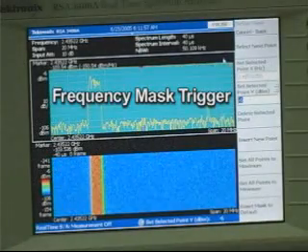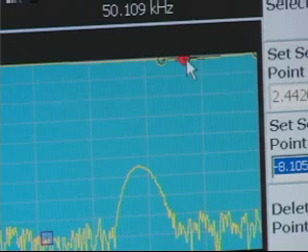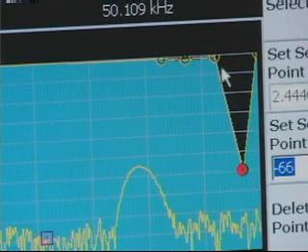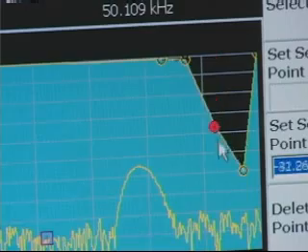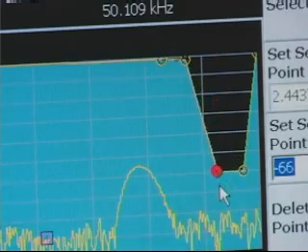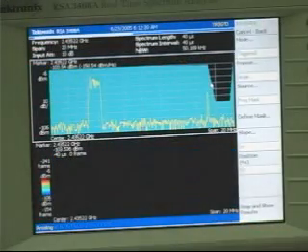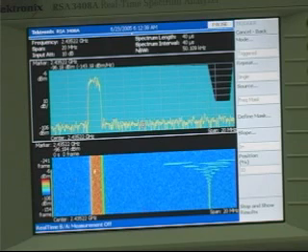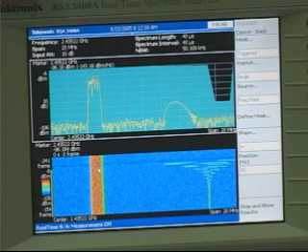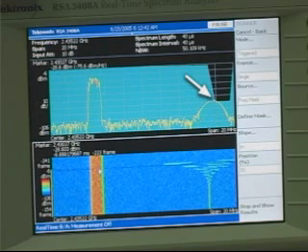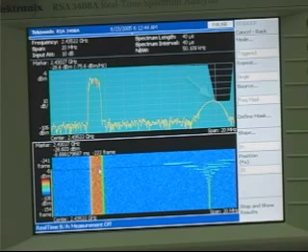Using the frequency mask trigger, you can create a free-form spectral mask on the display with hundreds of control points. You simply define an area near the interfering signal, specify an acquisition length, arm the trigger, then just wait for the acquisition. The RTSA triggers when a signal violates the mask by entering the black area of the display.